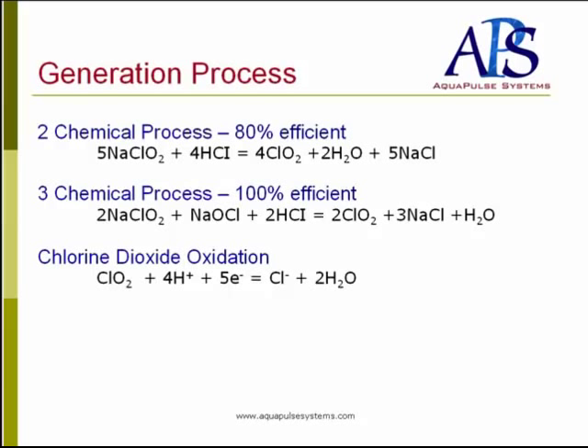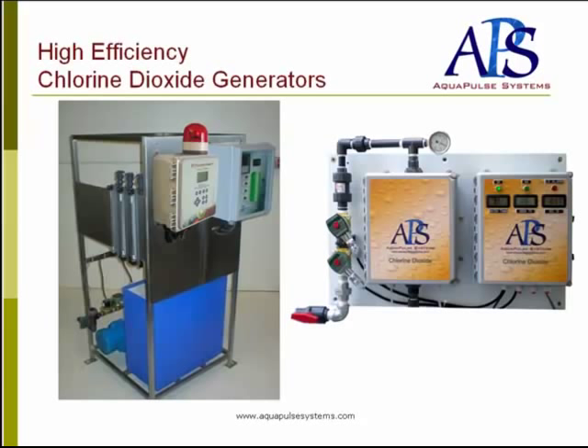The three-chemical process utilizes sodium chlorite, sodium hypochlorite, and hydrochloric acid, and efficiencies approaching 100% can be achieved. Generators come in all different shapes and sizes. These are the three-chemical systems on the left-hand side, where you make chlorine dioxide instantly, and it's stored in a small tank as you can see at the bottom of the frame.